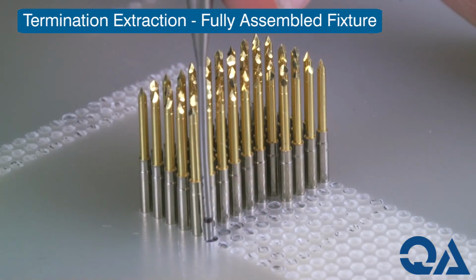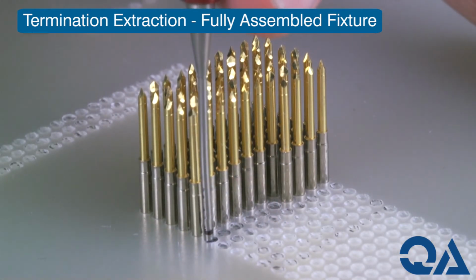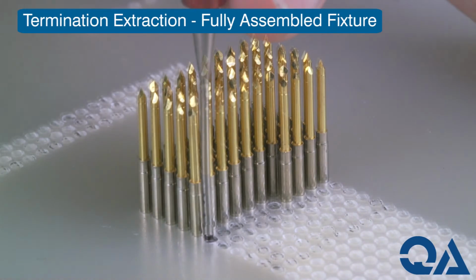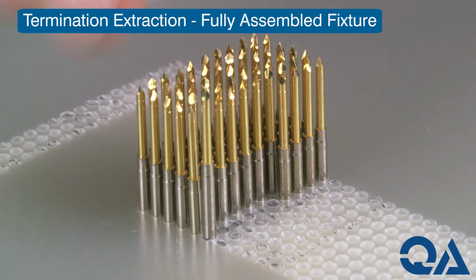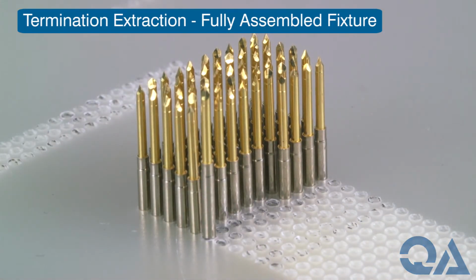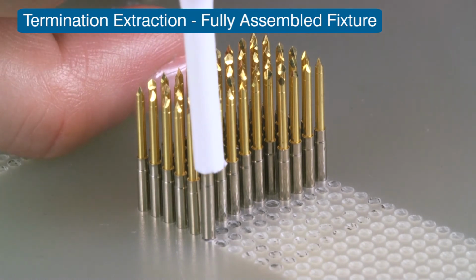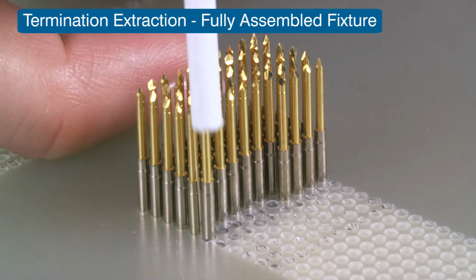Lightly tap only to the point where the mark on the tool shank aligns with the top of the probe plate. This ensures that the termination pin is at the same height as the one previously removed. A replacement probe is then reinstalled.